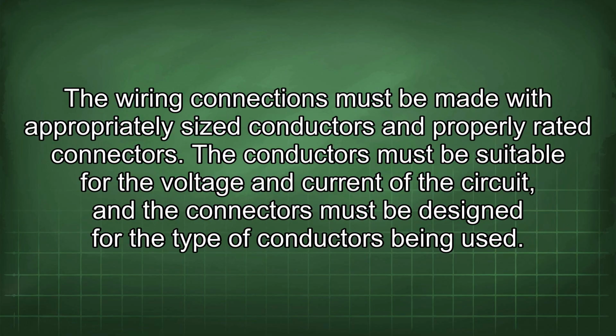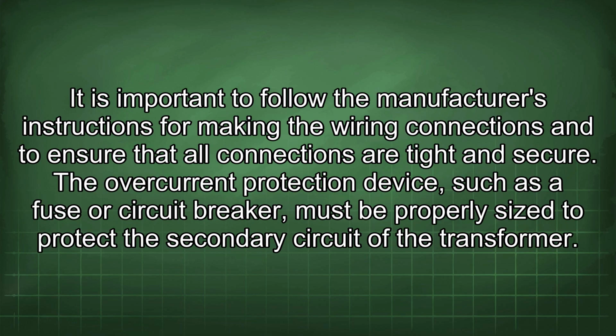The wiring connections must be made with appropriately sized conductors and properly rated connectors. The conductors must be suitable for the voltage and current of the circuit, and the connectors must be designed for the type of conductors being used. It is important to follow the manufacturer's instructions for making the wiring connections and to ensure that all connections are tight and secure. The overcurrent protection device, such as a fuse or circuit breaker, must be properly sized to protect the secondary circuit of the transformer.